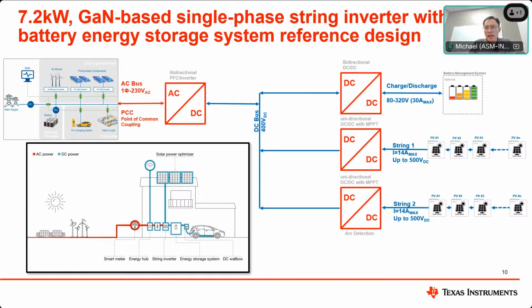The current to charge and discharge the battery pack is rated for 30 amps. For a 240 volt battery pack, this would translate into a maximum charge and discharge power of 7.2 kW. The third building block is the bidirectional AC-DC, which is rated for single phase up to 3.6 kW only. The reason was that we limit the output current in this single phase application to 16 amp RMS. At 230 volt, this translates into 3.6 kilowatt.